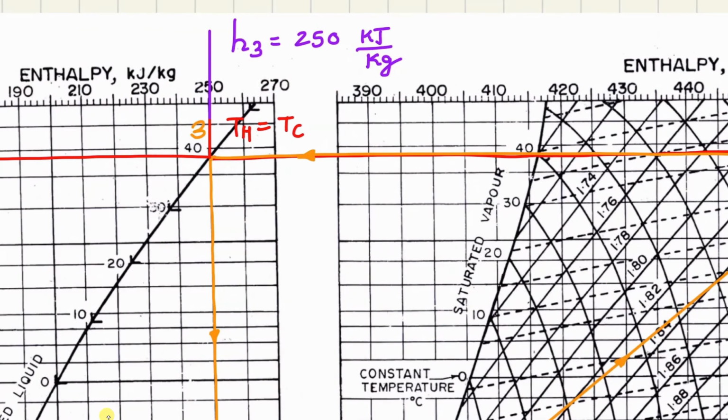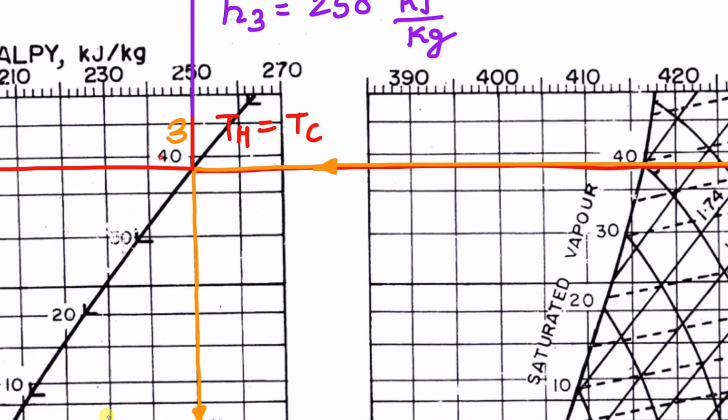Now observe the point here. Even though 40 is written here, this line is not 40. Remember, that is a pressure line. Here you can see these right angles are there. Those are temperature, and here also there will be a right angle, that is not visible because I have already plotted it. So here there will be a right angle, so that temperature is 40. So be careful, this is a pressure line, and these are temperature values on the saturation curve. So this is 40, higher temperature, so I have marked higher temperature first. This is 40 degrees Celsius.